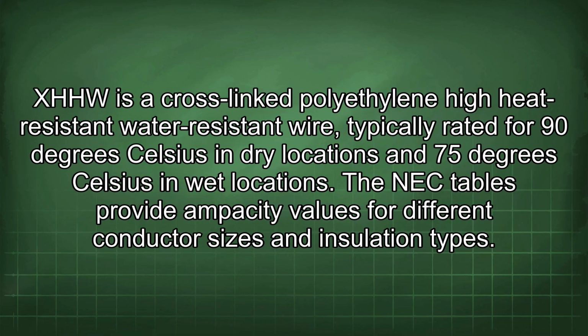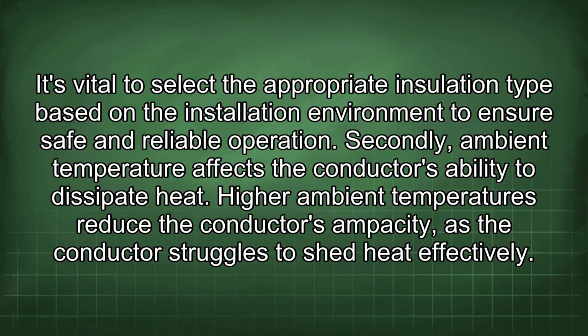XHHW is a cross-linked polyethylene high heat resistant water resistant wire, typically rated for 90 degrees Celsius in dry locations and 75 degrees Celsius in wet locations. The NEC tables provide ampacity values for different conductor sizes and insulation types. It's vital to select the appropriate insulation type based on the installation environment to ensure safe and reliable operation.